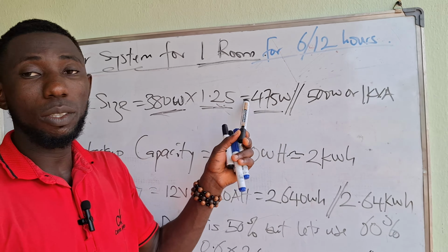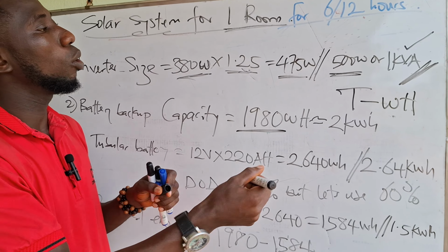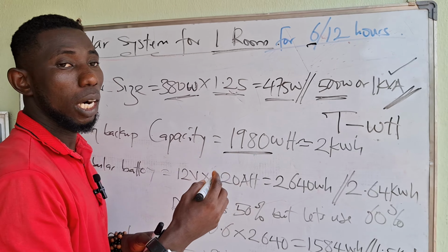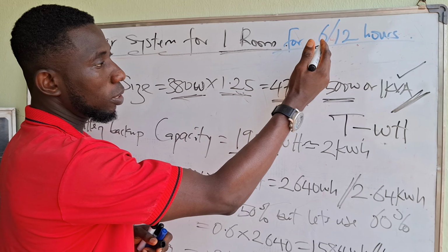From our previous calculation, our total watt hour gives us 1980 watt hour. If we approximate this, it becomes 2 kilowatt hour. That is the size of the battery bank we need to power the load for 6 hours. Remember, we are calculating for 6 hours before we go over to 12 hours. So our total battery bank to power everything for 6 hours gives us 1980 watt hour, which is approximately 2 kilowatt hour.